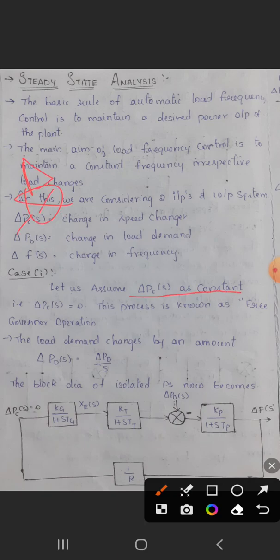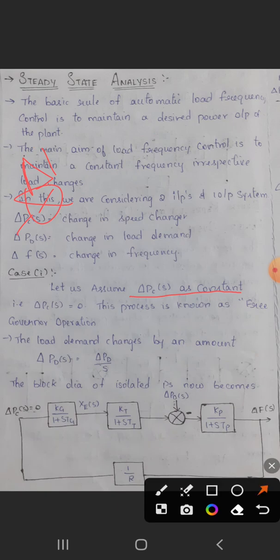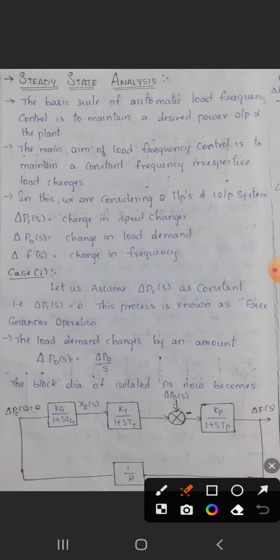Here we have delta PC of S and delta XE, and additionally delta PD of S, with delta F as the final output. Delta PC of S is constant and will be zero — this is called free governor operation. The load demand changes by an amount: delta PD of S equals delta PD divided by S.